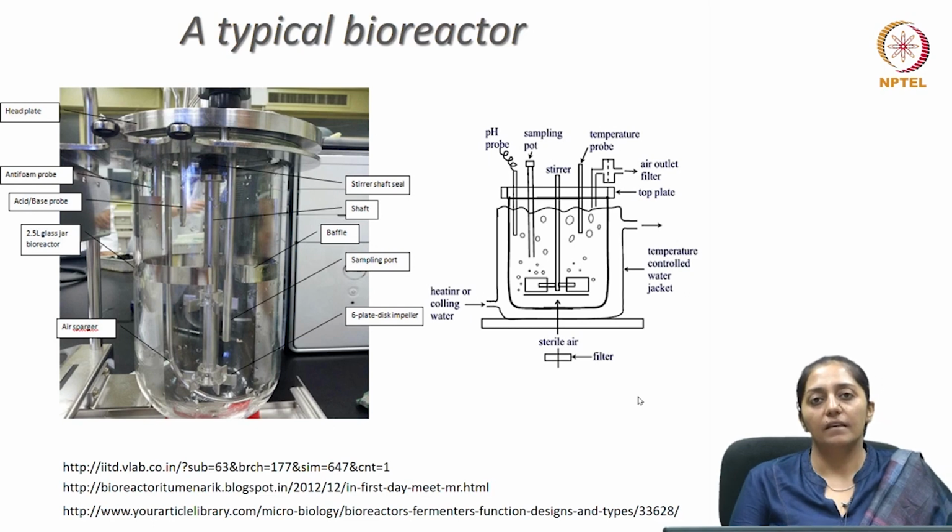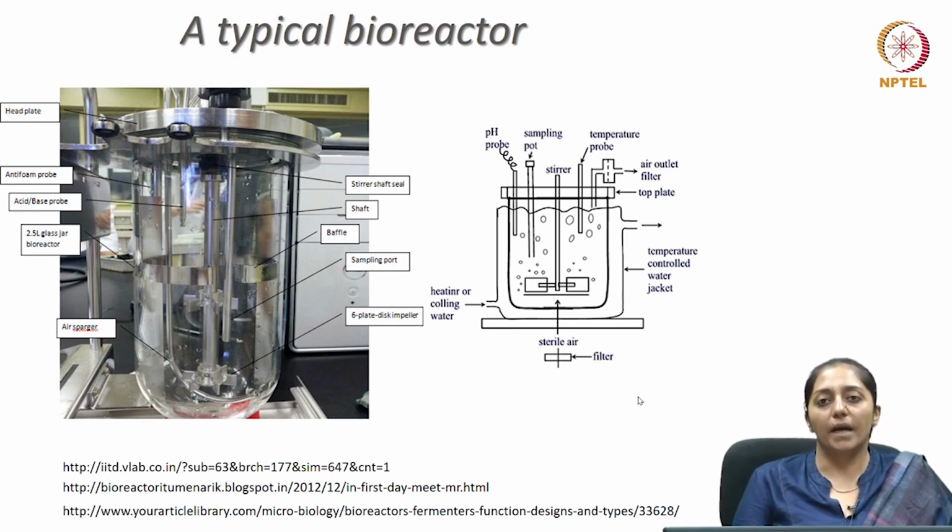As you can see on the slide, this is a schematic for a typical bioreactor with its different parts which we discussed earlier. There is a head plate on the top, then inside the glass vessel at the center you will see the shaft which has impellers attached to it. The photograph shown has a 6-blade disc turbine impeller, which is mostly used for microbial fermentations. Then you will see a half U-shaped rod ending beneath the bottommost impeller. This is the air sparger.